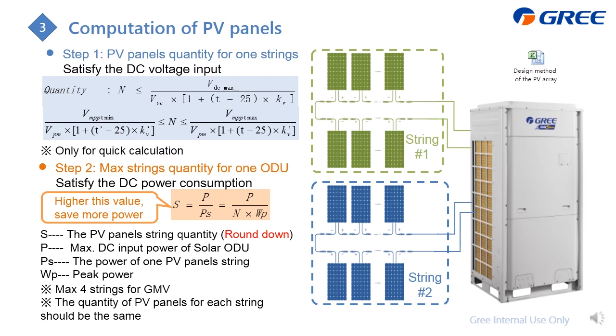This is the detail for doing the PV system selection. When you open the Excel file, it displays this table. This part is the parameters you get from the PV panels, including the five I mentioned. This part is the parameters from our outdoor unit—for example, once you select the outdoor unit, you check the service menu and input the max DC input here, and the MPPT range here. Then input your local ambient temperature during daytime, and you can get the value directly.